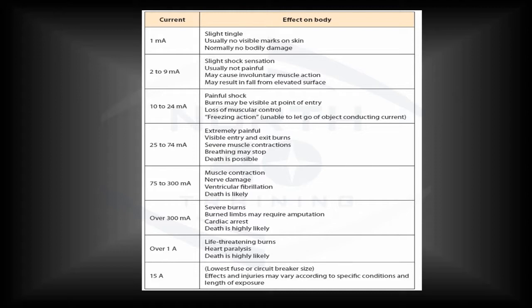Secondary related injuries really become a huge deal at this 2 to 24 milliamp range—and obviously they happen beyond that too. But the difference between actual bodily injury from the shock itself versus injury because you jerked your hand and hit it on metal objects inside that cabinet is way skewed toward secondary injury, not the shock itself.